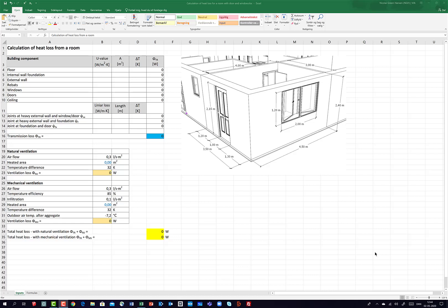In this video I'll show you how to calculate the heat loss from a room. In this room there is a door and a window. The room size is 3.5 times 4.5 meters — that's the outside measurement; the inside measurement is 4 times 3 meters. The U-values I use in this example are fictive — you use your own U-values in your project. I'll start with the floor and I assume without floor heating.